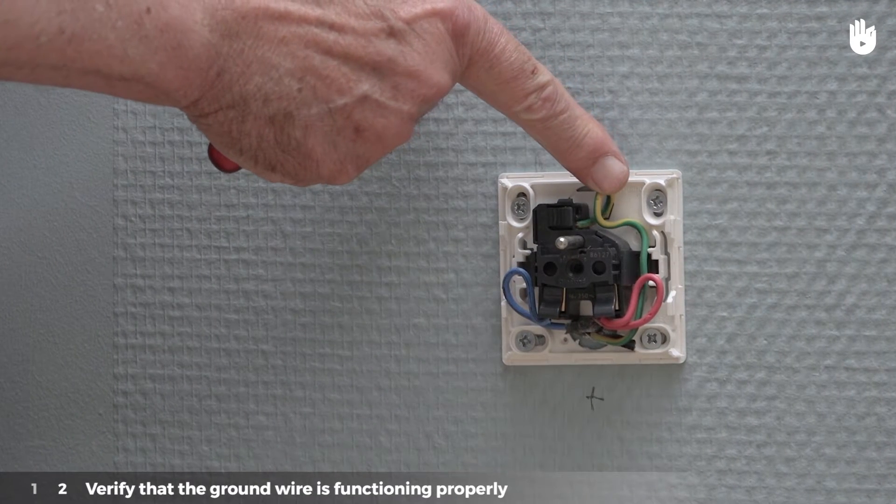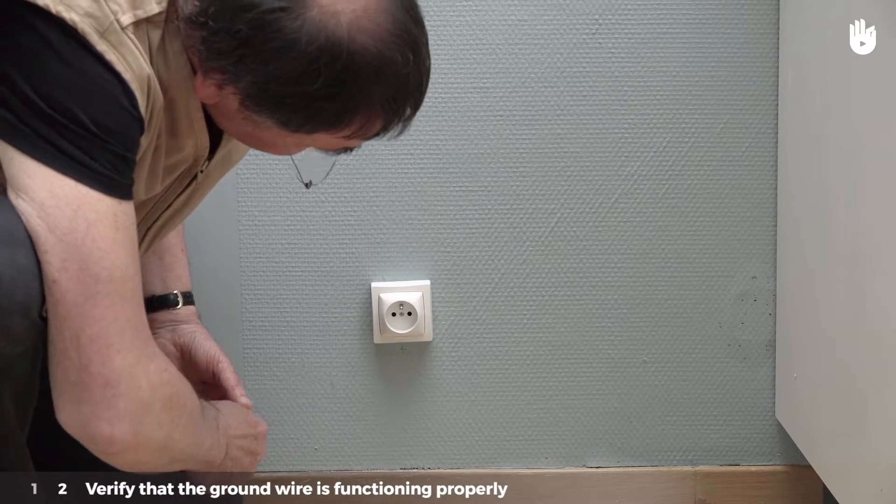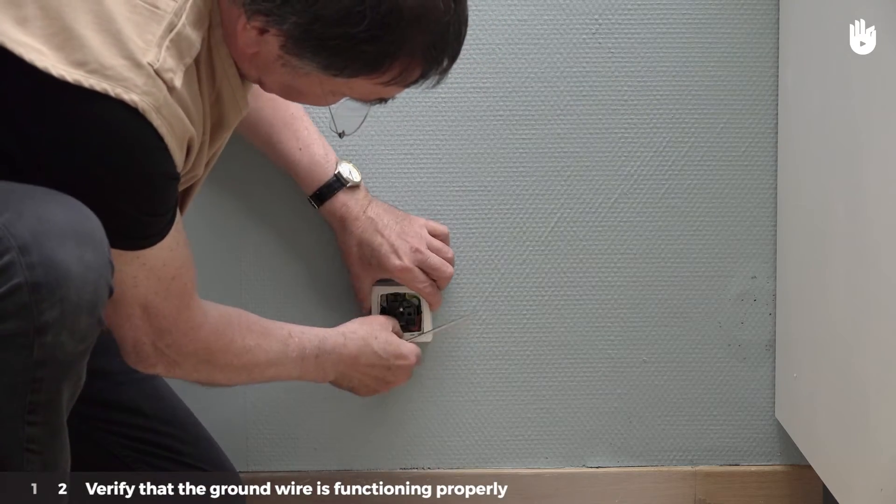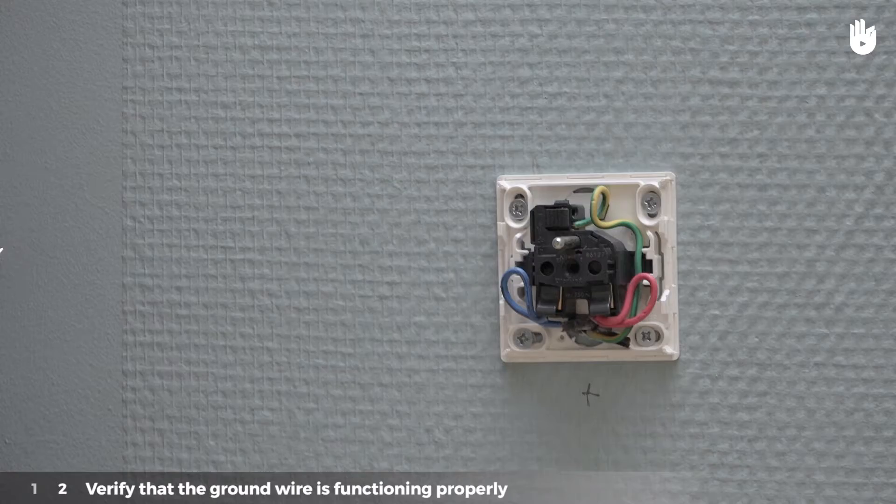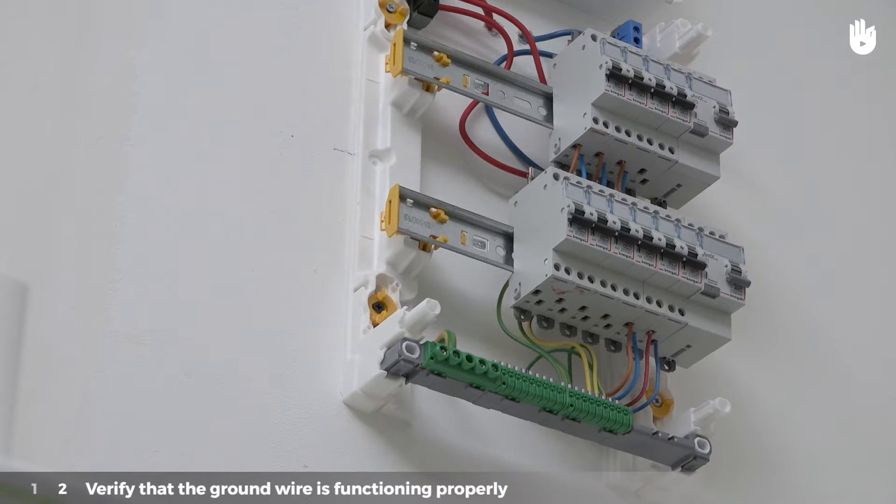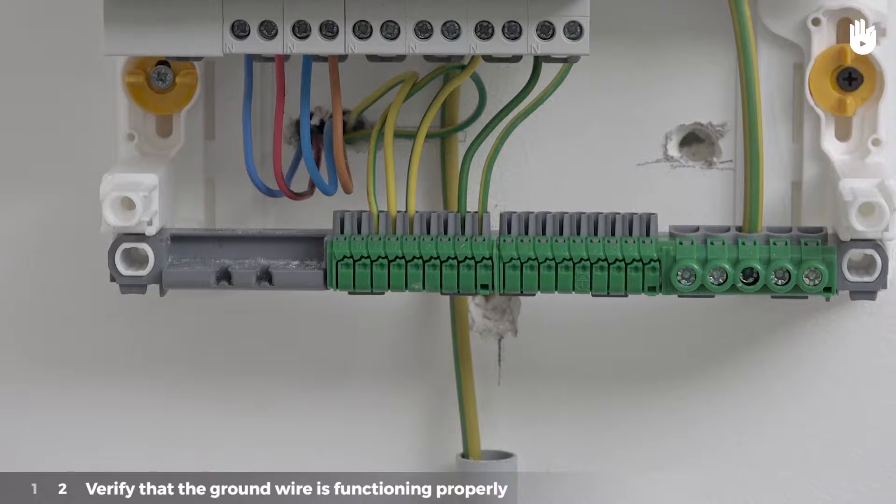Step 2: Verify that the ground wire is functioning properly. The ground wire makes it possible to dump leakage current safely. Therefore, it is important to verify that all of the outlets have a ground stud. This ground stud is connected to the grounding strip or the terminal block of the electrical panel via a green and yellow wire.